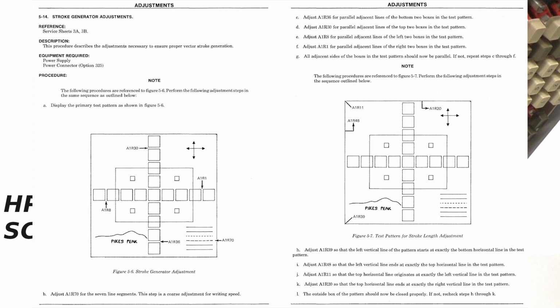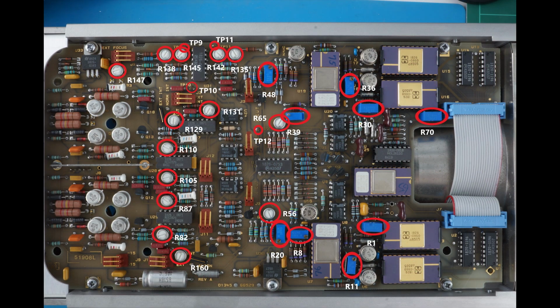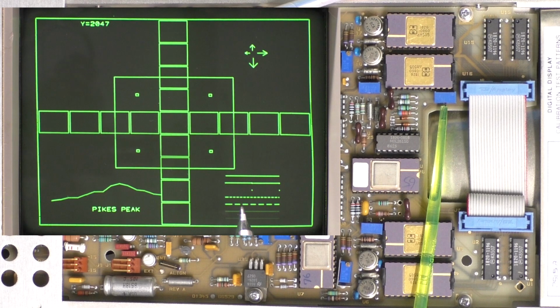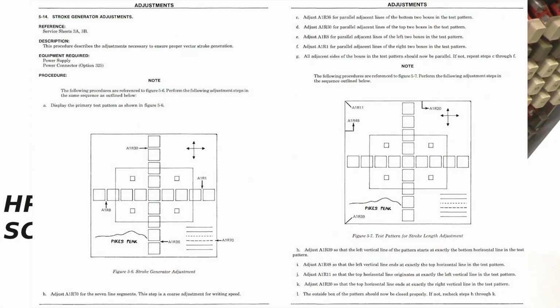5-14-B, coarse writing speed. Locate R70 on the A1 board. This is the writing speed adjustment. Adjust R70 for the 7 line segments, ensure even size and spacing. Moving on to stroke generator. 5-14-C through G. These ensure lines drawn are parallel.